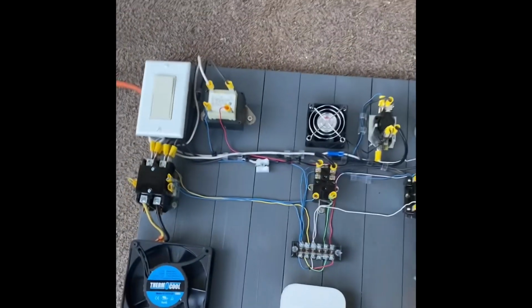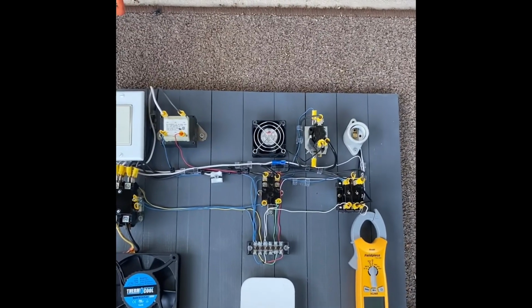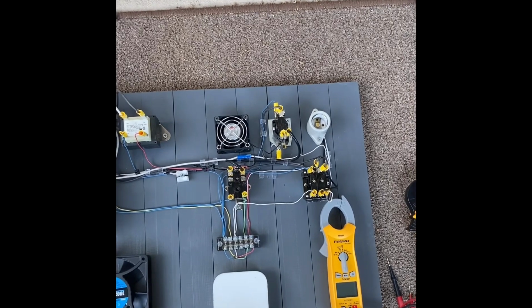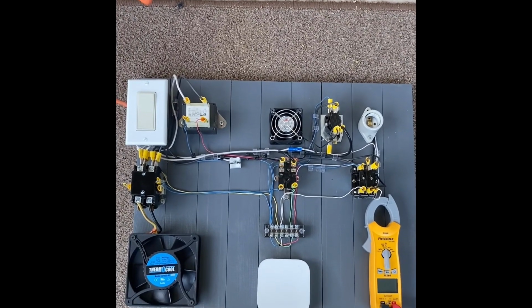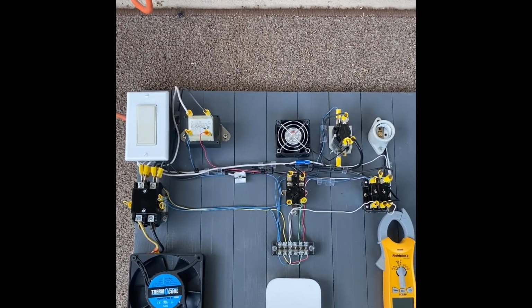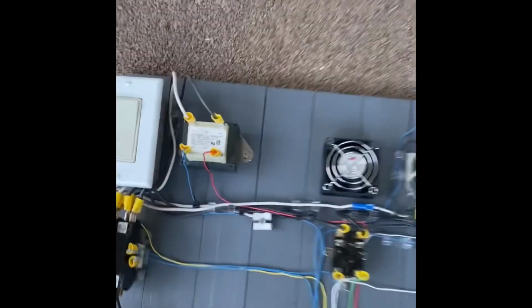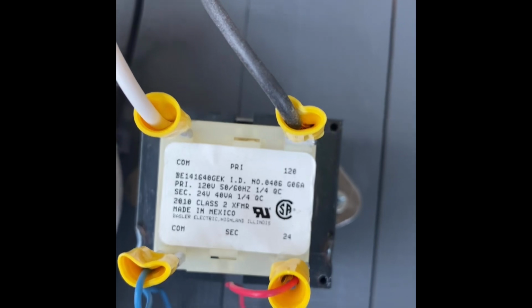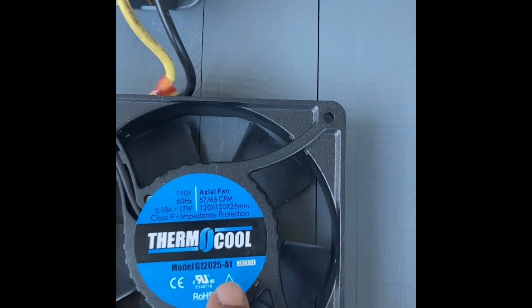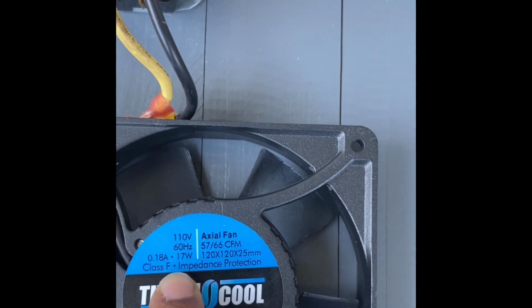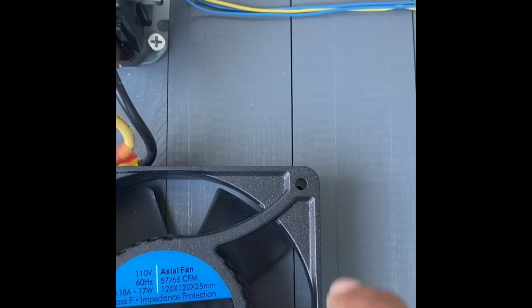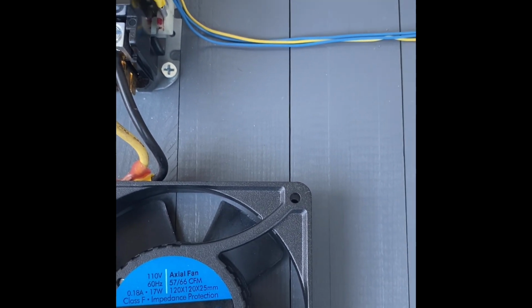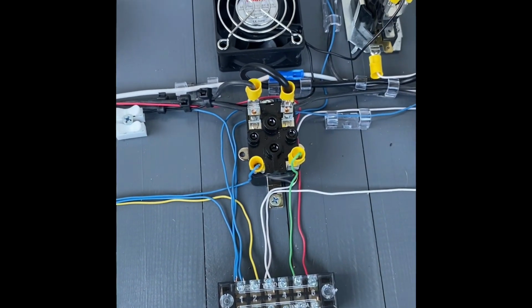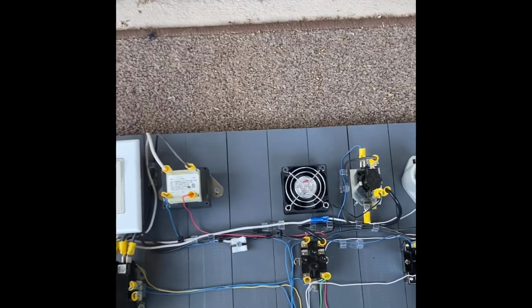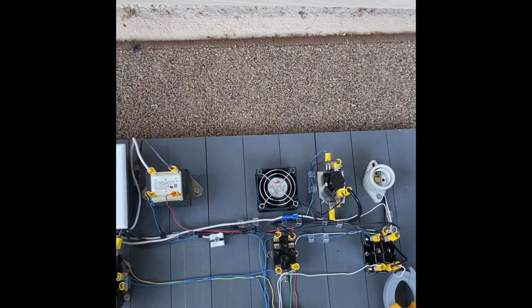But I'm gonna turn this training board on, and we're gonna check everything with the multimeter, so you guys can have a pretty good understanding of how to use it. But before we use it, we're gonna check something real quick. I have a 120 volt transformer, and also I have a condensing fan motor, and the amperage for this is 0.18. So I'm gonna be checking power, checking amperage, and also checking this relay just to see when it's normally open, normally closed. And we're gonna be checking power, so you guys understand how to use it.